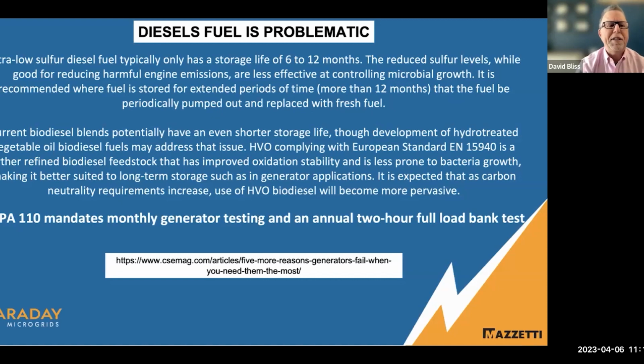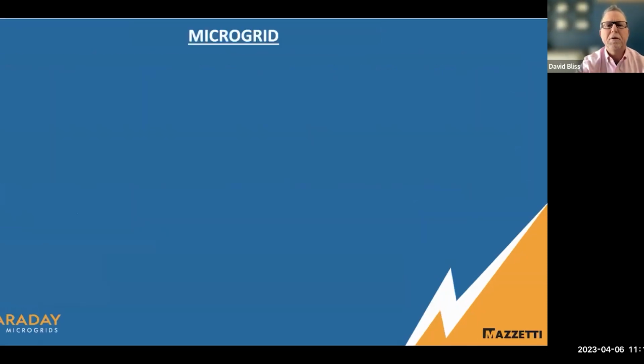Down toward the end you'll see that NFPA 110 mandates monthly generator testing and an annual 2-hour full load bank test. Those come with expense, and you need certified technicians, etc.